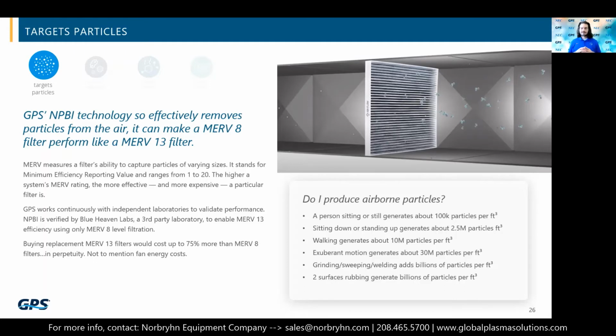What I mean is a certain filter rating, let's say a MERV 8, and there was a study done in this specific case. A MERV 8 filter is a very standard commercial air filter for kind of minimum level filtration. And so there are smaller particles in the air than will get caught by a MERV 8. A lot of particles, especially those that are infectious, will just pass right through a standard filter, which is why you see organizations like ASHRAE recommending to upgrade your filters from MERV 8 to MERV 13, which is a great idea.